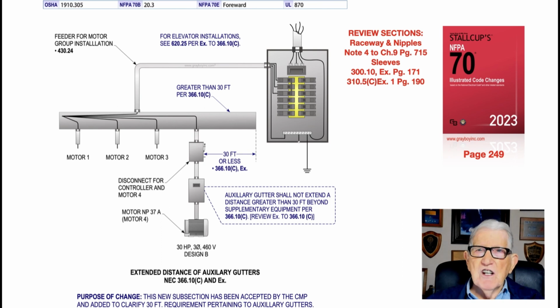Then you have to deal with sleeves. A sleeve is open on both ends, and it protects cables and PVC and so forth. And 300.10 exception on page 171 gives you this information. Then you have a sleeve from a panel board that you see in the illustration that extends up through a suspended ceiling, 10 foot or less in length, connected in one end, open on the other. And 310.5(C) exception 1 on page 190 deals with this type of sleeve.